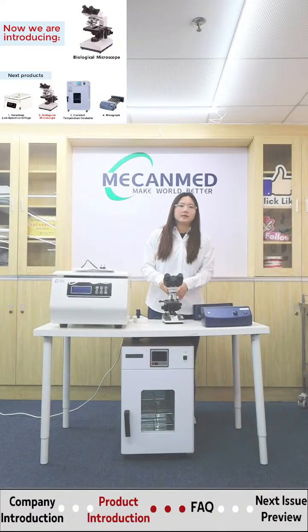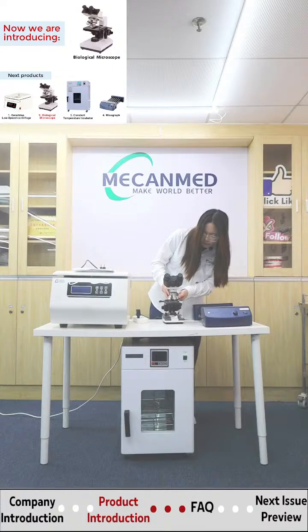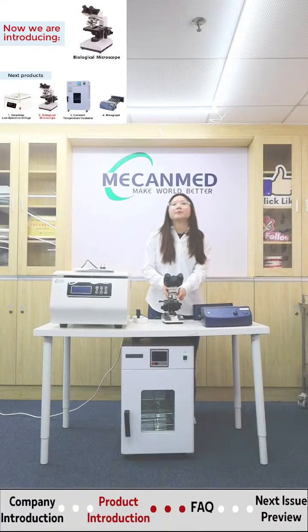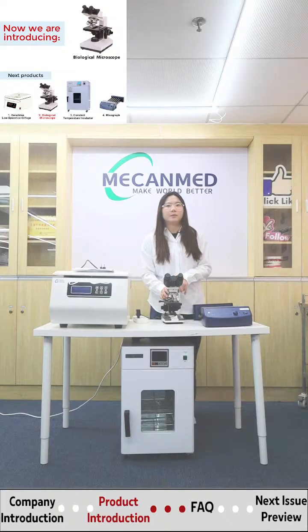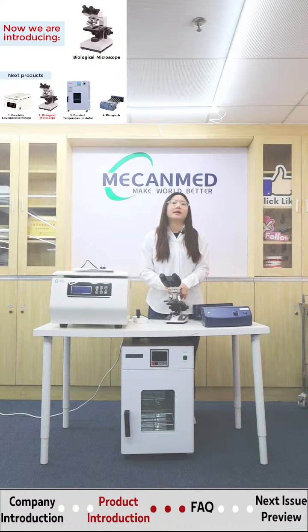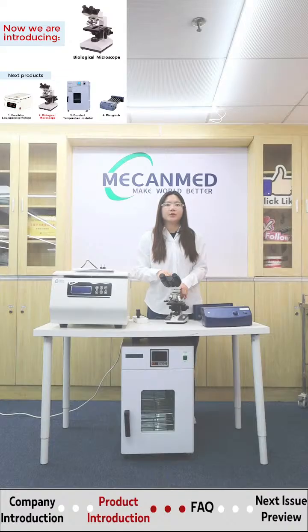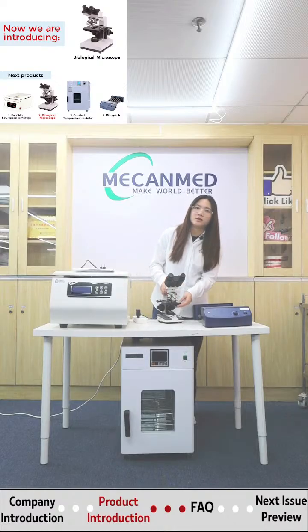Okay, let's start with the 4 times objective. Rotate the nosepiece to align the 4 times objective with the light path. Use the coarse focus knob to bring the sample into rough view. Then switch to the fine focus knob to sharpen the image until a clean image is obtained. Now please, let's crank up the magnification. Rotate the nosepiece to align the 40 times objective with the light path.